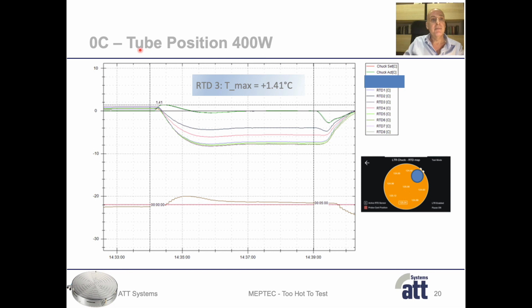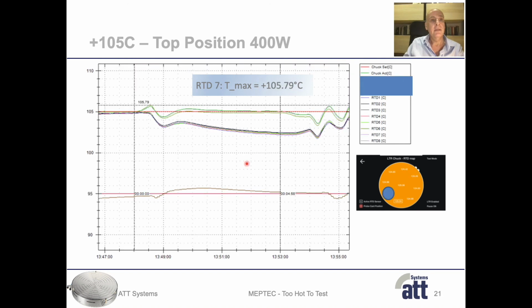Same picture at the tube position. In this case, RTD3 became the control sensor, and the maximum temperature was measured with 1.4 degrees C before the system fully dissipates the energy and controls the temperature very stable around the set temperature of 0 degrees C. Then we changed the chuck temperature to plus 105 degrees C and basically repeated the test. Top position with 400 watt.